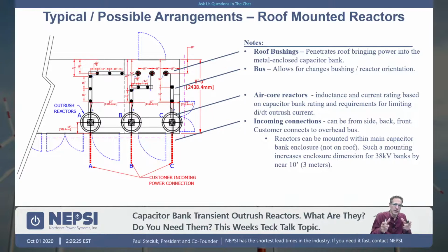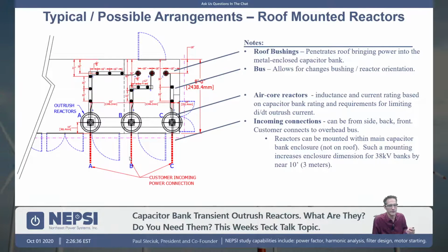When we put the outrush reactor on top of our enclosure, what we are expecting at that point is that the customer is going to come in from overhead. And in the renewables environment, this is very common. They have their collector system, they have breakers within the substation itself, the bus work, and they'll park the metal-enclosed system somewhere close by to that bus work, and they can jump down with a set of jumpers to our equipment. That's shown by these red lines here. So they will come right into those outrush reactors.